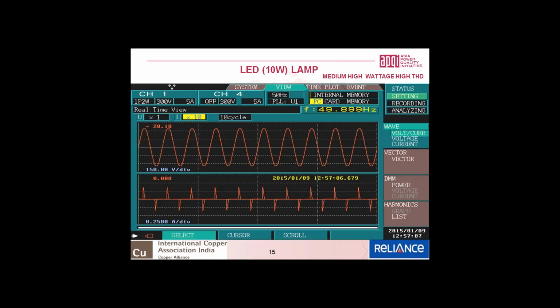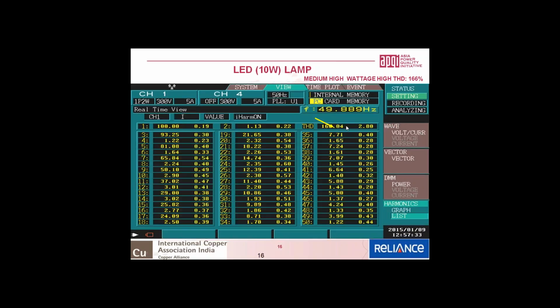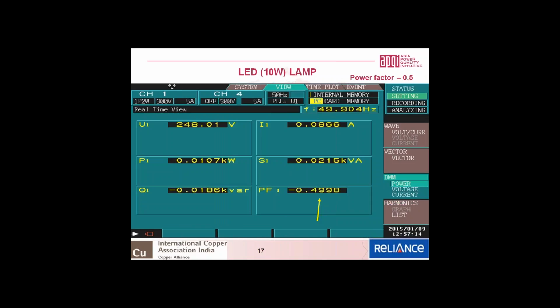Yes, what we say is correct. The total harmonic distortion is almost about 168%. Therefore, this LED has a very high harmonic content. Not only are the harmonics very high, you can see the power factor.